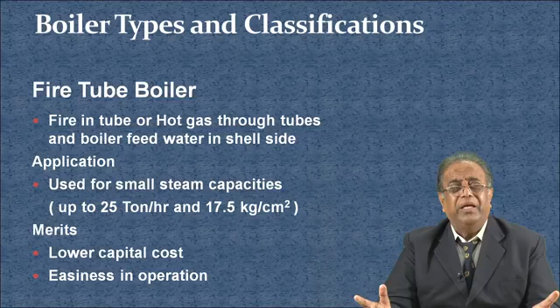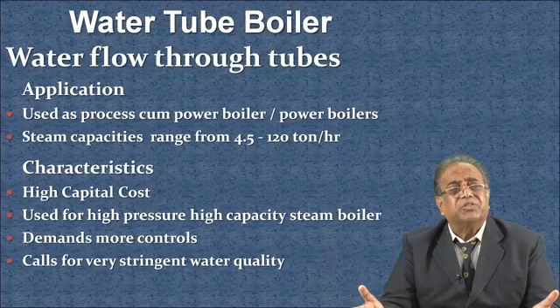There is another type of boiler, we call it the water tube boiler. When you consider the water tube boiler, water flows through the tubes. Application: used as process cum power boiler or power boilers, with steam capacities ranging from 4.5 to 120 ton per hour. Characteristics: high capital cost, used for high pressure, high capacity steam boilers, demands more control, and calls for very stringent water quality.